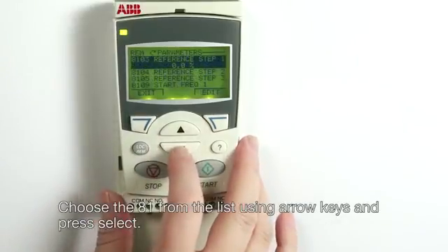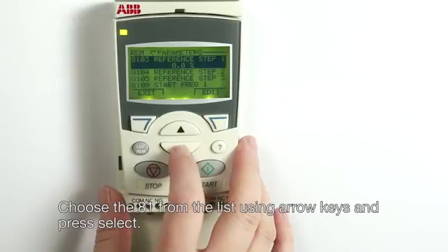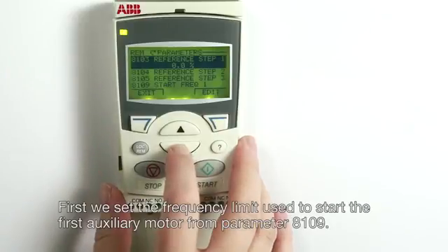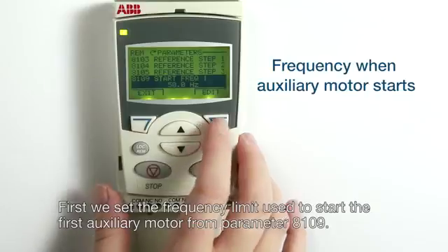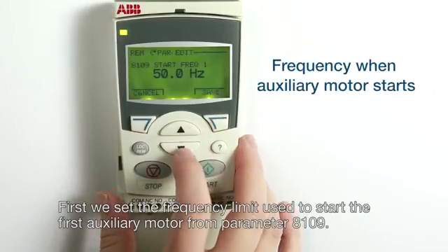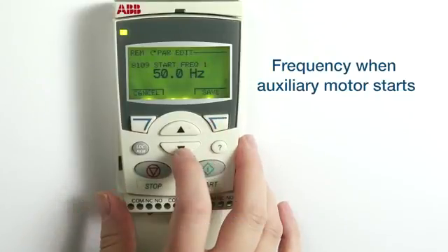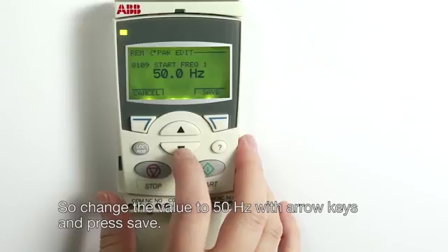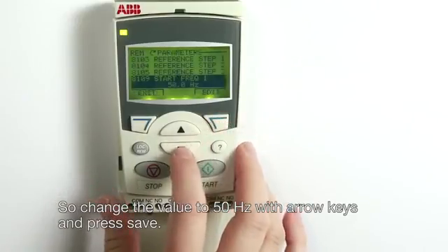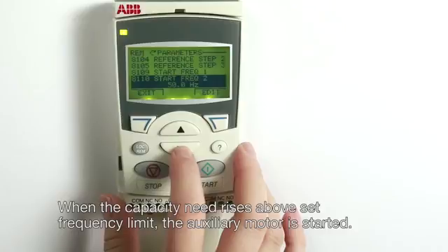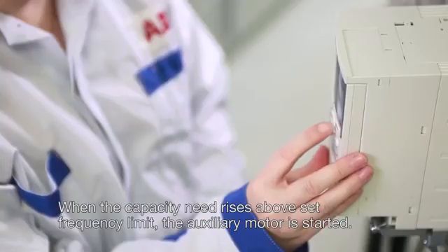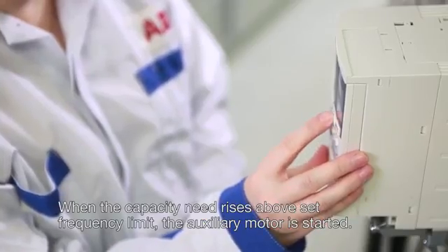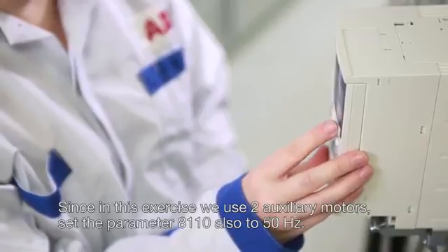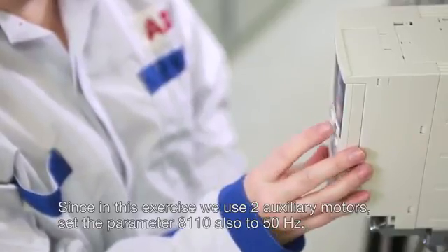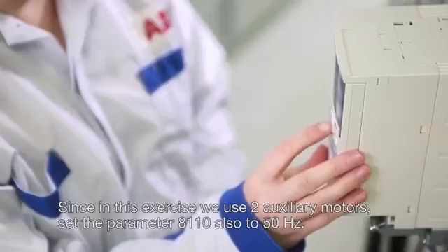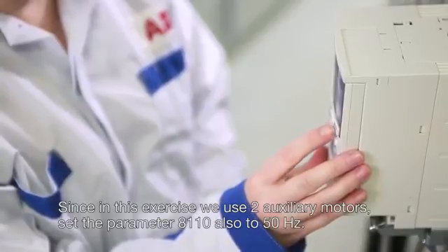Choose the 81 from the list using arrow keys and press Select. First, we set the frequency limit used to start the first auxiliary motor from parameter 8109. So change the value to 50 Hz with arrow keys and press Save. When the capacity need rises above the set frequency limit, the auxiliary motor is started. Since in this exercise we use 2 auxiliary motors, set parameter 8110 also to 50 Hz.